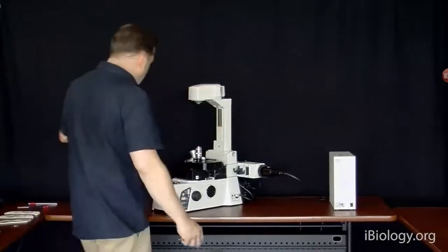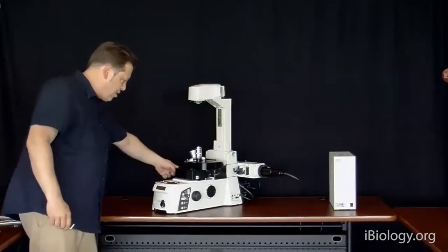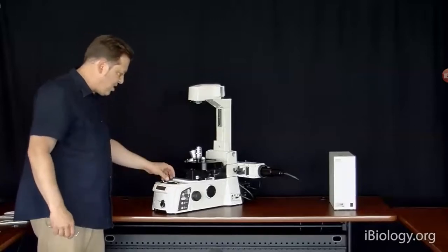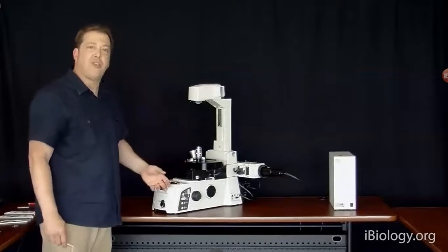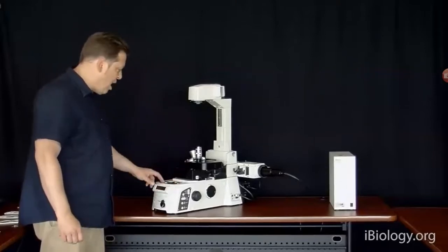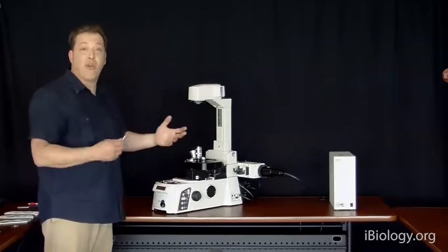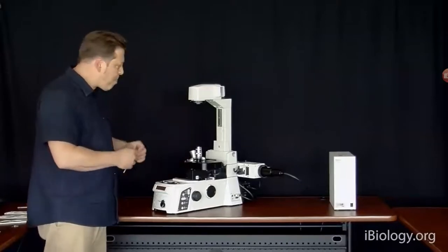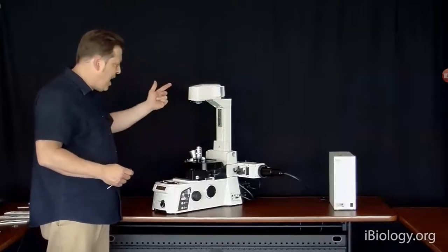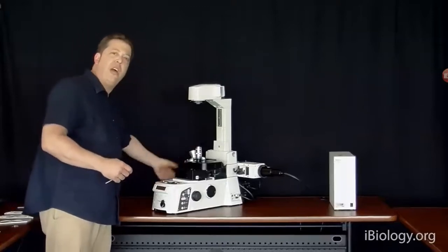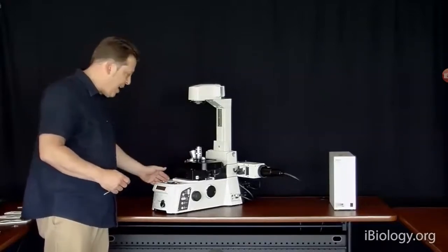Below here, this is a relay lens in the microscope where the light will come up through to the eyepieces. And this is also a wonderful place if you wanted to put something like an IR cut filter for optical trapping again, or any sort of a cut filter for laser safety, as well as many fluorescence strategies will have a multi-band mirror to reflect fluorescence up to the specimen, and then have a wheel that will switch channels to get multiple images sequentially on a detector.